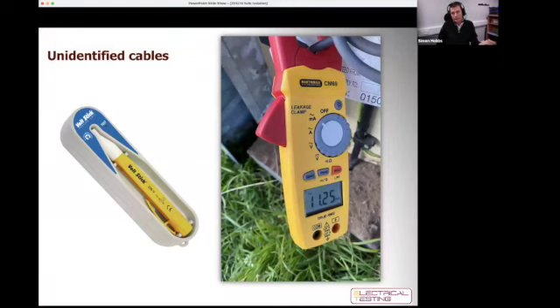And if the volt stick tells you that the cable is live, you can assume that it is live. But if the volt stick tells you it's dead, you still have to assume that the cable is live. Once the insulation's been removed from the cable using live working techniques to reveal underlying conductors, a contact voltage indicator should be used as a means of proving dead in the usual way. Then with regards to isolating that cable, it may be that it needs to be pot-ended and a new feed supplied, or potentially it could be traced in a better way at that point. Okay, so that's touching briefly on unidentified cables.